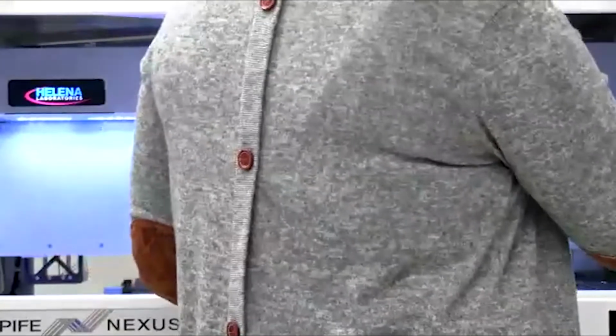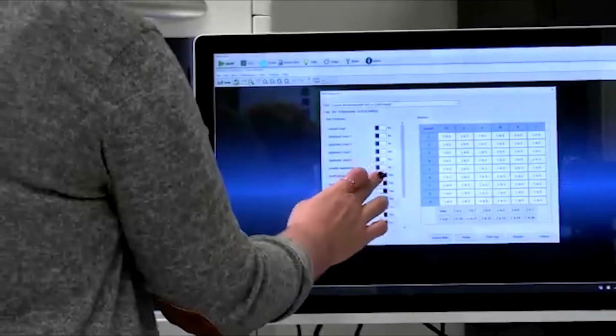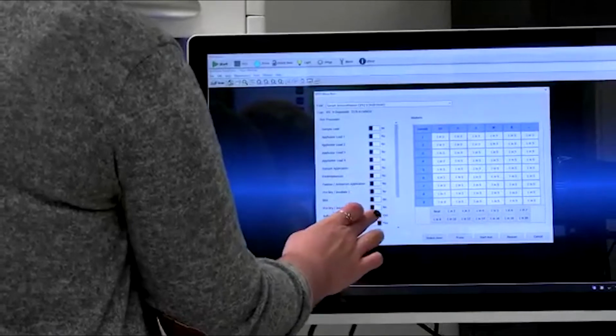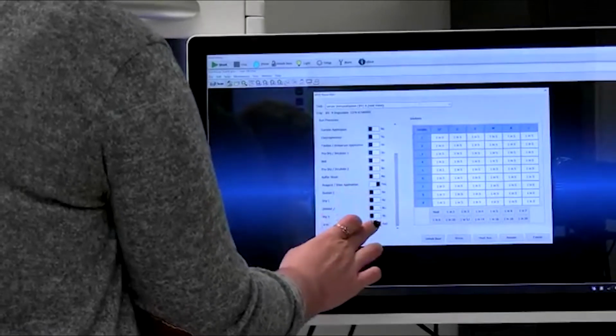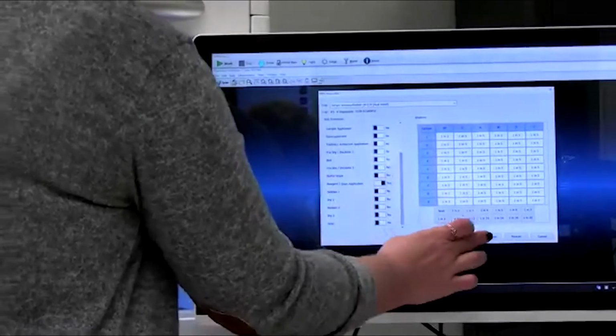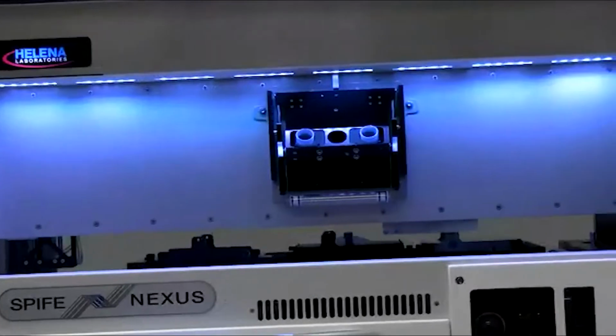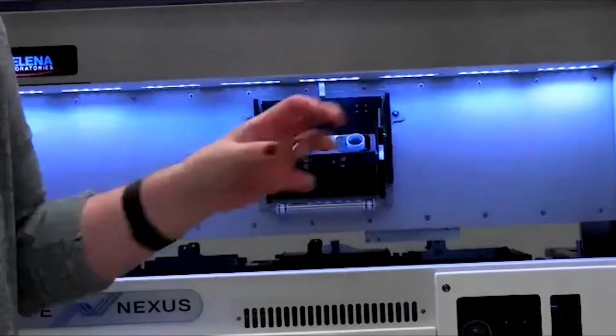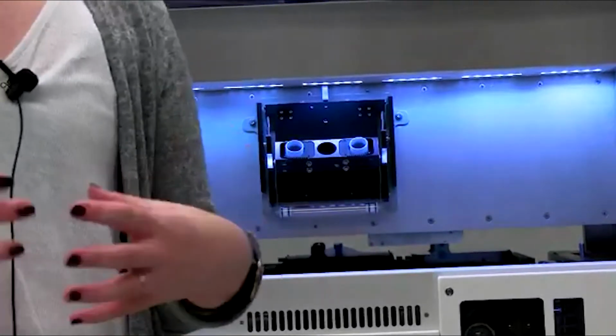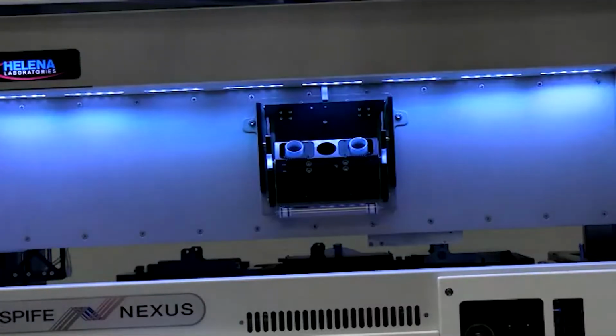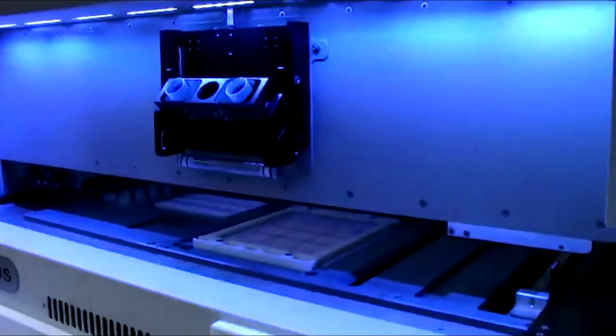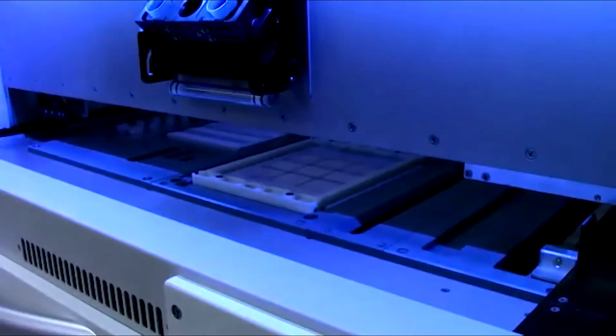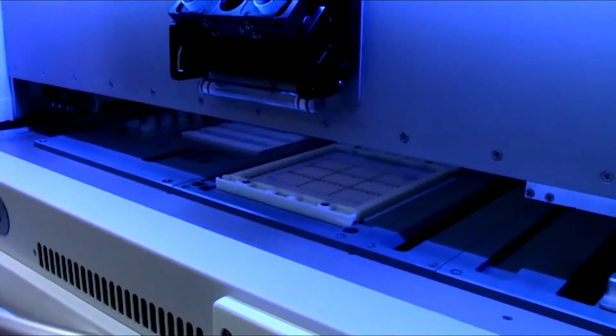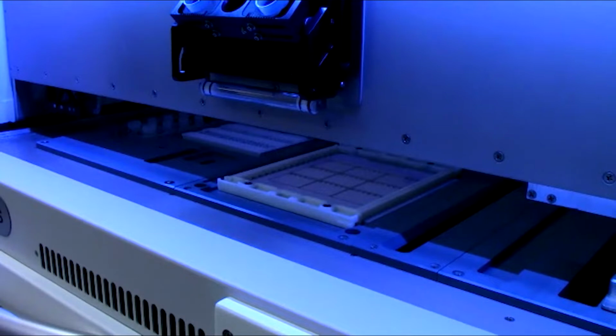Close this, start. And like I was saying before, I can choose from my start menu any process that I want to run. So I'm going to leave only reagent stain application selected. And then I can press my start button. And it's still going to go through the scanning process, but this time our pre-start scan is only going to check for the components necessary for the steps that I selected. So instead of checking all the pieces, it only checks to make sure that I had my cassette in place for the staining process. So it's about to move into position and dump the stain.